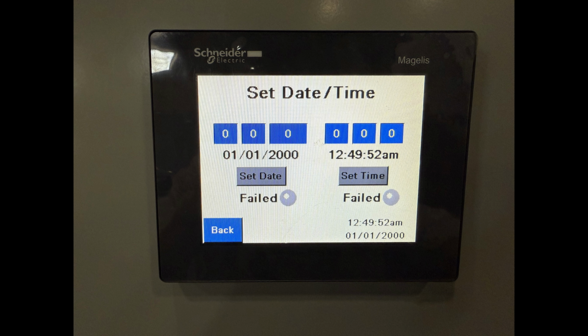We move on here, we can see the set date / time, and this actually helps. As you can see in the lower right corner, you actually do have the time and the year in there. This was before I had changed it back to its time in there. Obviously it is not January 1st, 2000. Happy New Year to everybody. But yeah, this has been my HMI so far, and now I will show you the pages for changing the automatic set points in auto mode and changing the variables in hand mode.